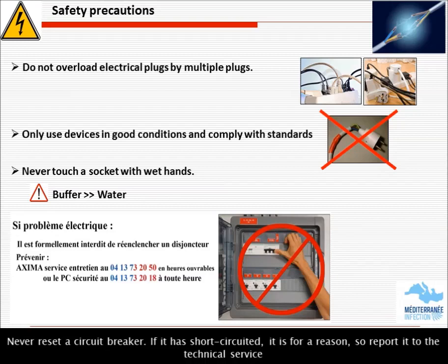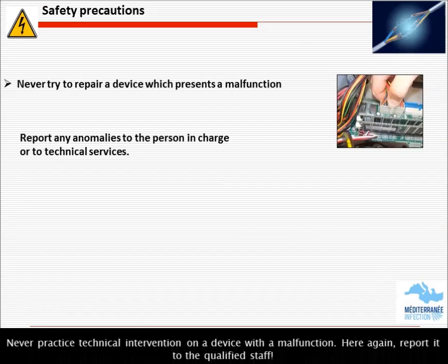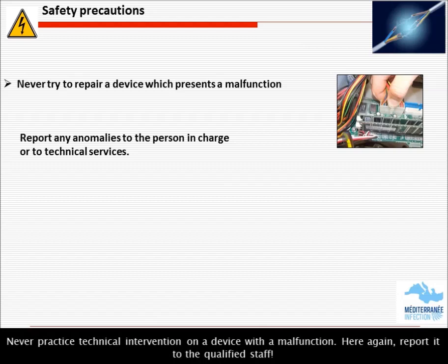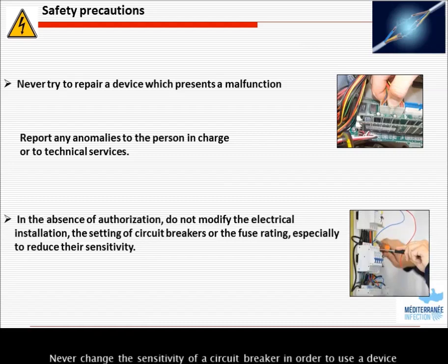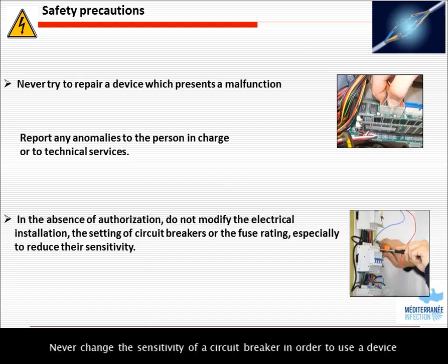If it has short-circuited, it is for a reason, so report it to the technical service. Never practice technical intervention on a device with a malfunction. Here again, report it to the qualified staff. Never change the sensitivity of a circuit breaker in order to use a device.